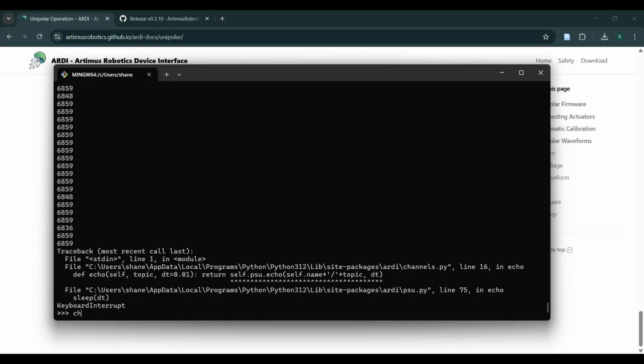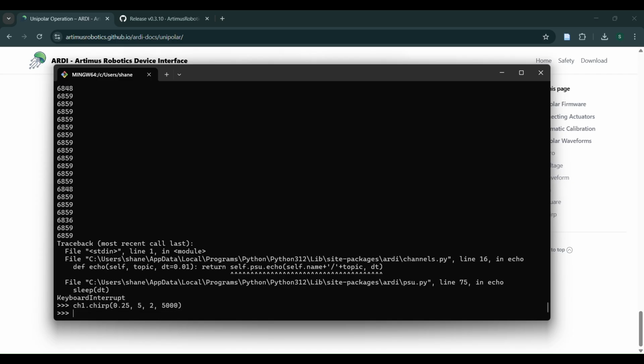Now I can program the voltage waveforms. On channel 1, I'll be using a chirp signal that varies in frequency from 0.25 Hz to 5 Hz over the course of 2 seconds with an amplitude of 5,000 volts. For channel 2, I'll apply a 6,000 volt square wave at 1 Hz.